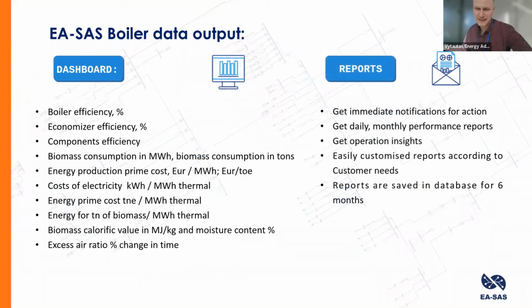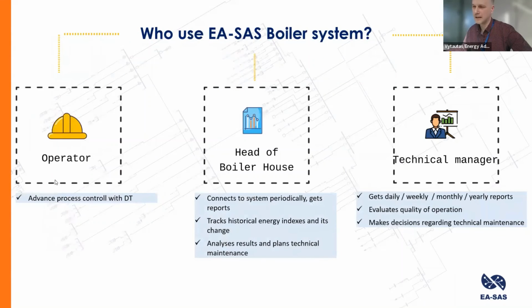Some outputs: many data, but also efficiency, economizer efficiency, components, energies in megawatt hours, cost of electricity, etc. You get reports like in a monitoring system, but also advanced process control, because it's a digital twin, not a monitoring system. The head of the boiler house connects to the system periodically, gets reports, tracks historical energy indexes, analyzes results, and plans technical maintenance. The technical manager gets daily, weekly, and monthly reports, evaluates the quality of operation, and makes decisions on technical maintenance issues.